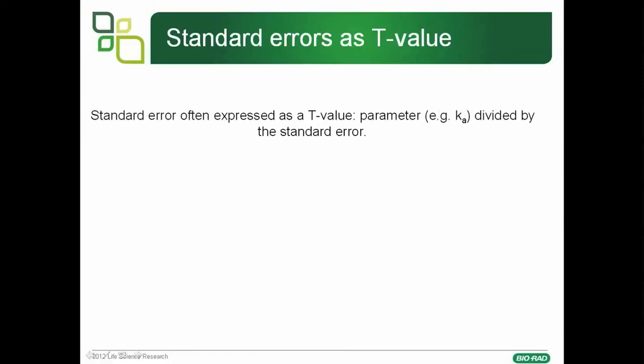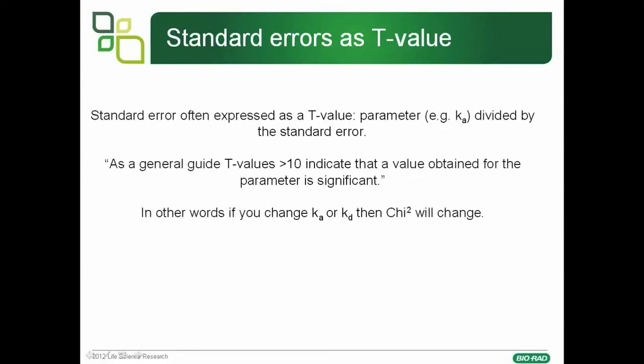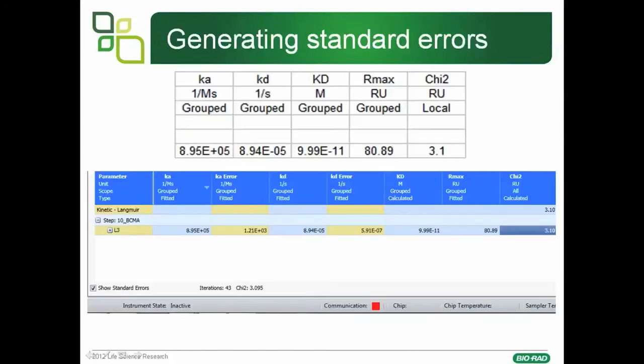People often express the standard error as a t-value. The t-value is generated by taking the parameter — for example Ka — and dividing it by the standard error. From the evaluation software manual, t-values greater than 10 indicate that the value obtained for the parameter is significant. In other words, if you change Ka or Kd, then the chi-squared fit to the model will change.